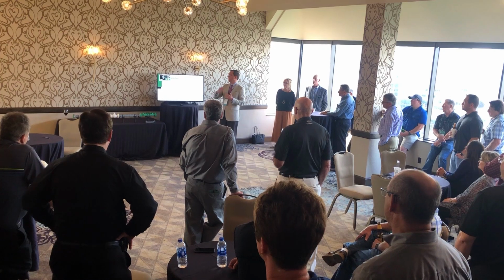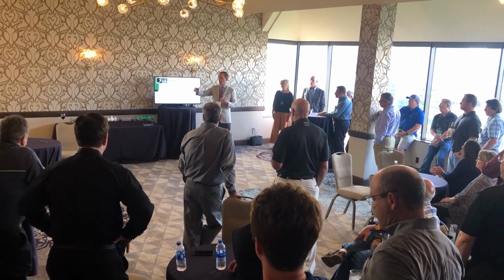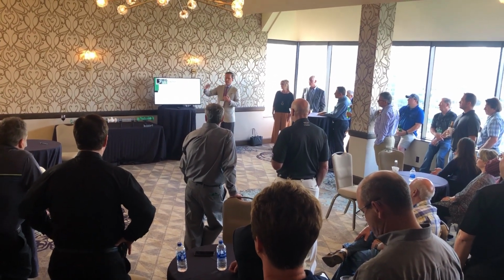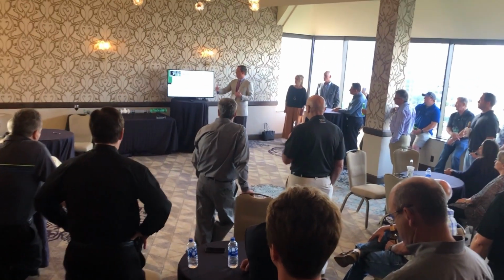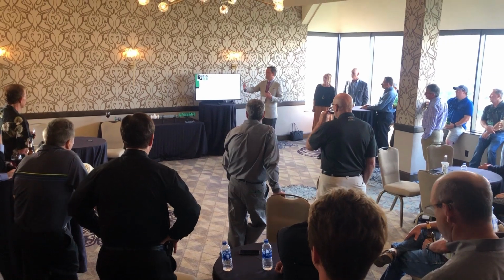And that was followed by a standard AGA 9, 10D, 5D meter. We only had 7D on the other side, or excuse me, we had 7D instead of 5D. And then a control valve that was going to be generating the ultrasonic noise. Then we had our design, which was the swirl generator, followed by the 2 flow conditioner arrangement, the meter, and then our noise attenuator downstream.